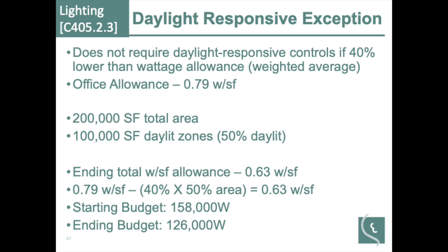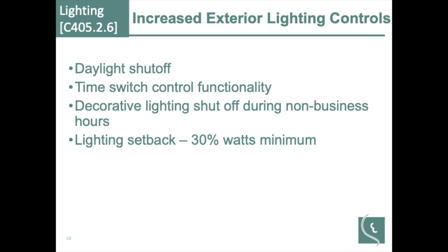Exterior lighting used to be just a shutoff, either daylight or time switch. Now it requires both. It also adds that you have to have a lighting setback of at least 30%, which is separate from turning off your landscape lighting. Landscape and facade lighting have to be off during non-business hours, and there's a couple of provisions for that in the code too. But this 30% could be dimming. It could be I'm going to turn the fixtures further away from my buildings off and leave the ones closer in on. Or you can just do it via occupancy sensors.